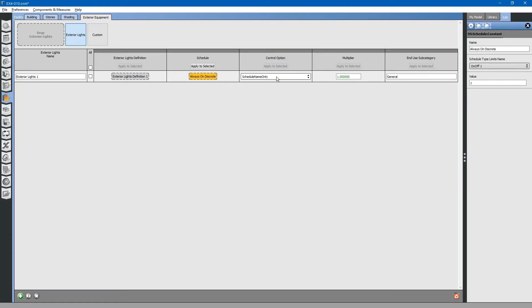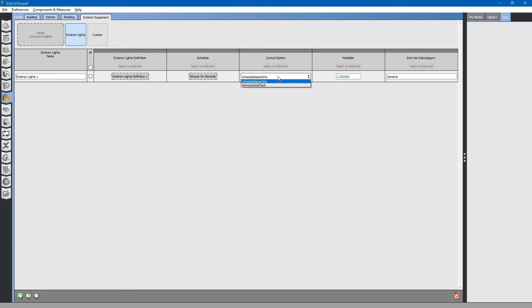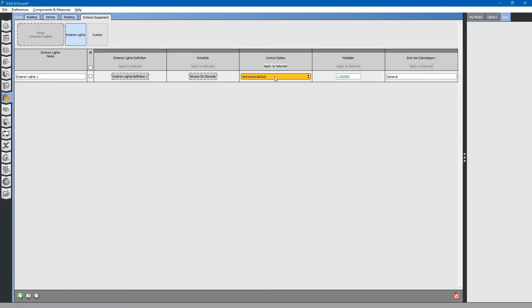Next, we will look at the control option. Control option specifies that the lights go on based on the schedule only. Alternatively, you can select astronomical clock. Using this combines the two. You will have a lighting schedule for the lights going on and off. The astronomical clock will override that schedule if it is saying that the lights should be on during the daytime. Basically, the astronomical clock is a photocell that shuts the lights off during daylight hours.